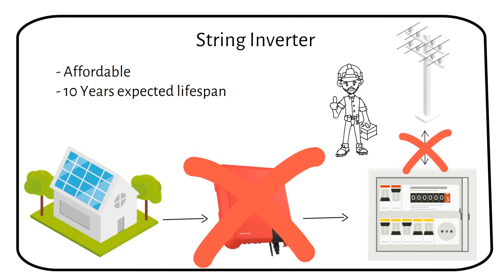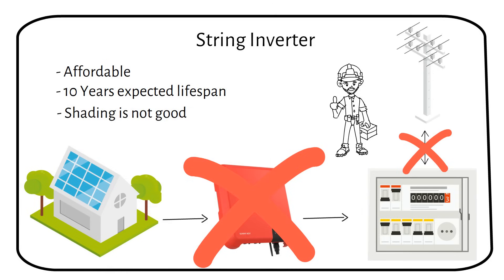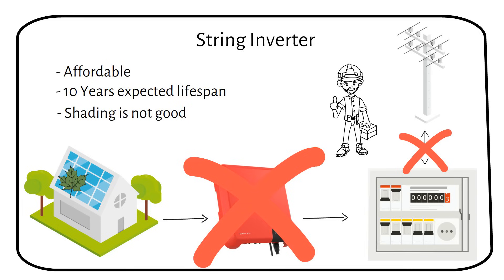Another downside is shading effects. If one panel in the string gets shaded from a tree or a building, the electricity made by the whole string drops. This differs from systems where each panel has its own inverter or optimizer. With a string inverter you also get less information about how each panel is doing, because it only shows how the whole system is working together, not each panel by itself. So while string inverters are a good low-cost option for getting into solar power, they do have some limits, especially if your roof gets shade or if you want detailed information on each panel's performance.